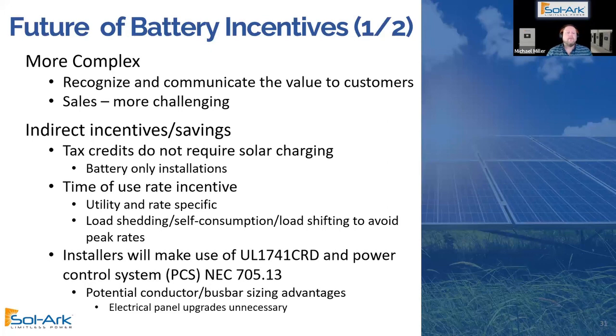Installers can make use of UL 1741 CRD and power control systems under NEC 705.13. This basically means the 120% rule is no longer in effect, and you can have a larger breaker feeding your solar array, or energy storage system, I should say. The energy storage system will maintain that it will not exceed the rating of the bus bar or the conductors, so that's going to be very important going forward.